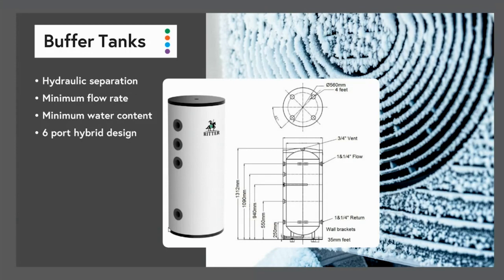So let's move to the next slide, where we go into a little more detail on buffer tanks. There, what we see is a 100-liter buffer tank with what's called a 6-port hybrid design, which I'll go into in a second. Another benefit of using the buffer tank is hydraulic separation. Hydraulic separation is creating two circuits. One is the primary circuit, the heat pump to the buffer tank. That circulation goes from the heat pump to the buffer tank, and then back out to the heat pump. So the heat pump can't actually see what's happening downstream of that buffer tank. It can't see the heating system, and it doesn't care what the heating system is doing. It's quite happy to just heat the buffer tank.